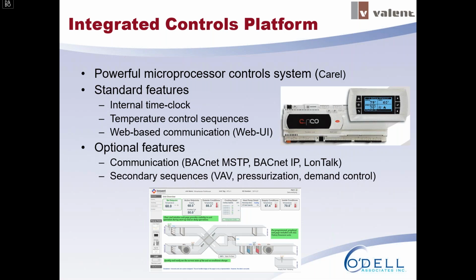The other standard feature that I believe is really powerful and valuable to the owner is that if you connect the microprocessor to the building's network with a simple Cat5 cable, by entering in an IP address, you can get a full, almost BAS in a box sort of solution. At the bottom there, you can see a picture of a typical graphic that would come up from connecting your unit to the building network. It saves a lot of time in troubleshooting and also setting up your systems. There are also optional features for that, being communication protocols, all the standard protocols with BACnet, MSTP, IP, and LonTalk. And there are some secondary sequences available to help with demand-based ventilation control, CO2 control, and variable air volume.